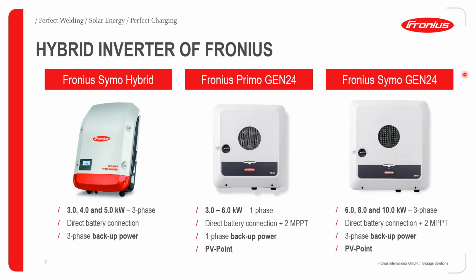Then moving on to the Fronius Symo Gen 24 Plus inverter. This is a 3-phase inverter, which comes in the following power variants: 6, 8, or 10 kilowatts. It allows for direct battery connection, and it has 2 MPPT trackers. It allows for full 3-phase backup power. And it also has a special PV Point feature, which provides an emergency output of 3 kilowatts max, as long as you have enough PV power being produced.